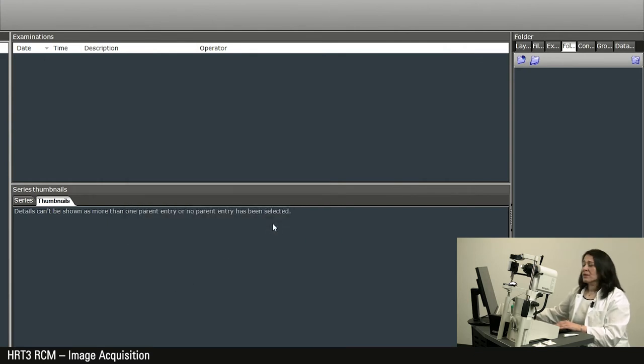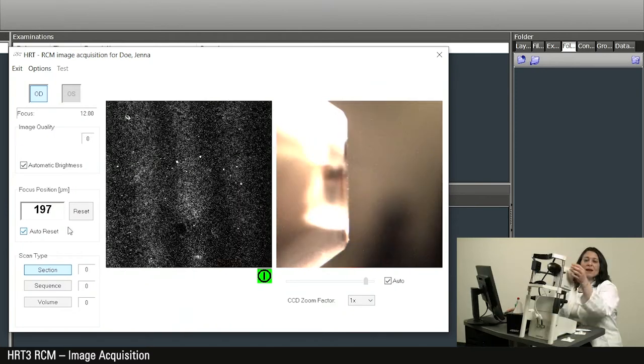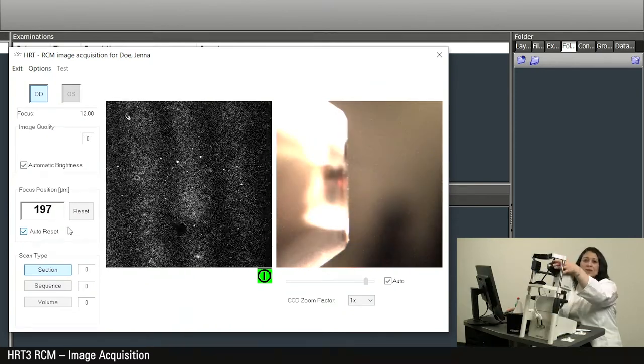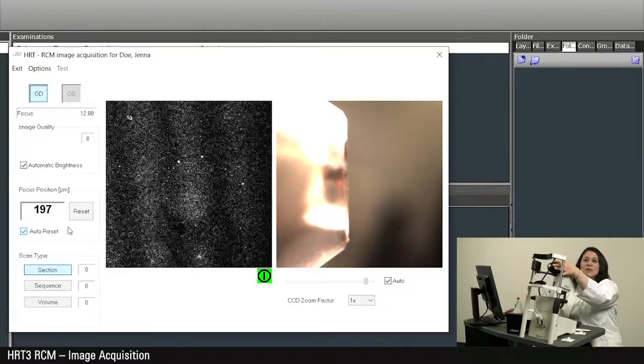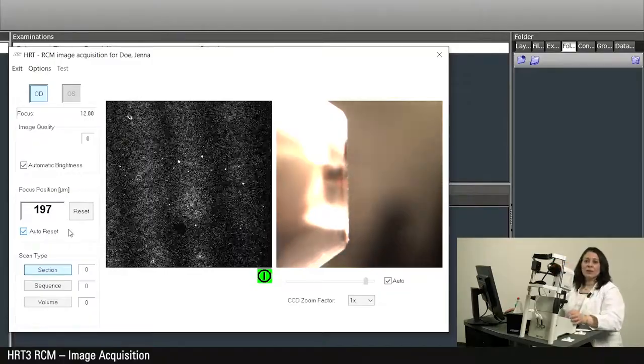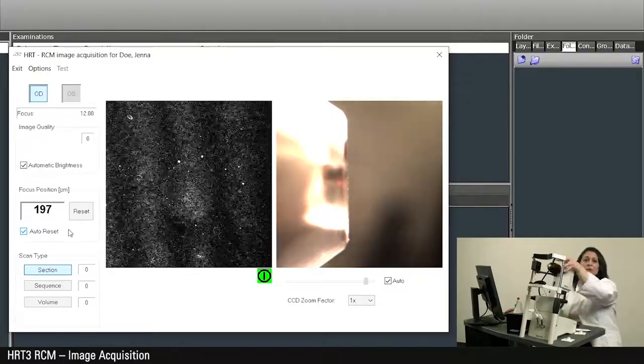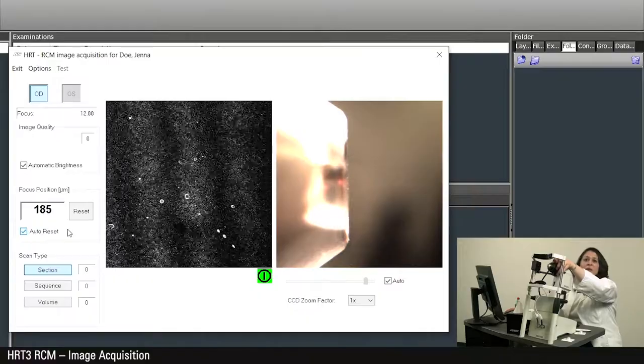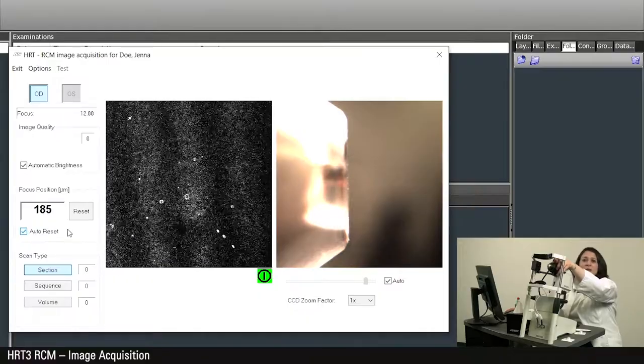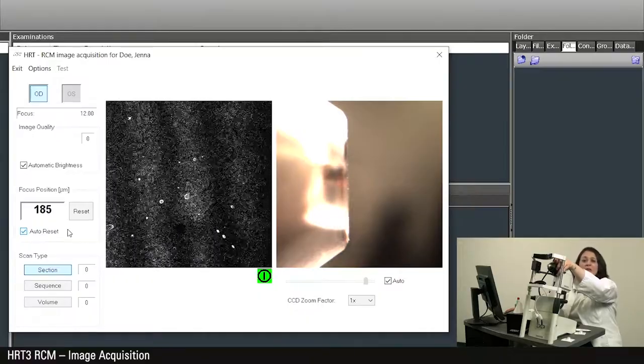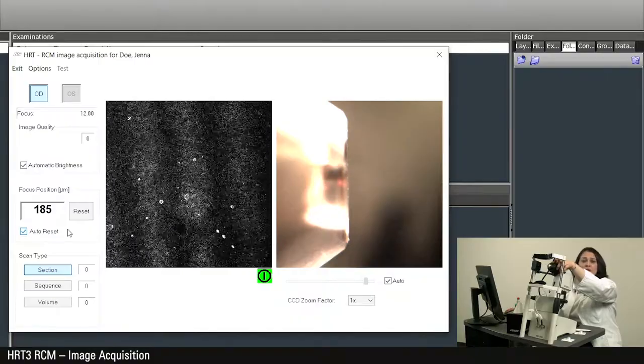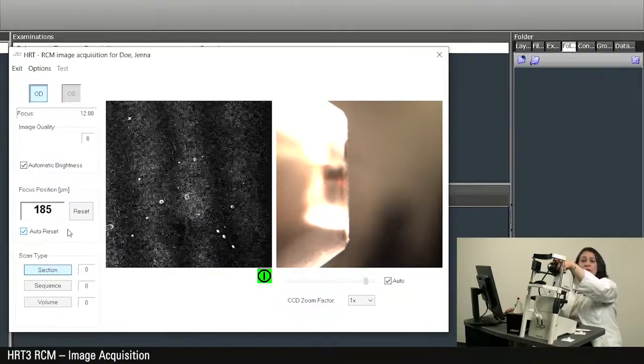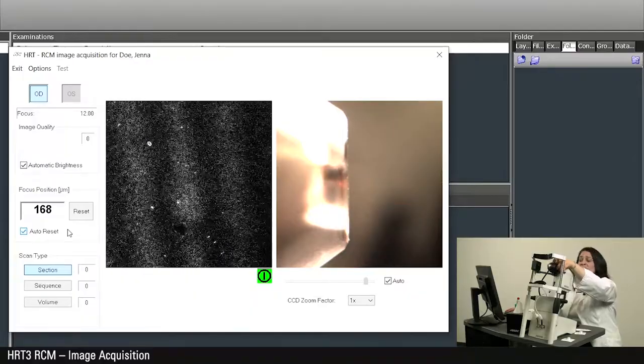Now you can start the camera. After we have already placed the sterile tomo cap on the objective lens, the focal plane must now be set to the anterior surface of the tomo cap. To do this, turn the objective wheel clockwise until a wide bright area appears. This should be done with a focus position between minus 150 micrometers and plus 150 micrometers corneal depth. When the image is brightest, press reset.